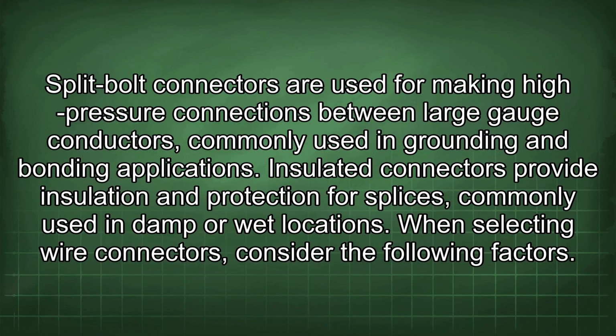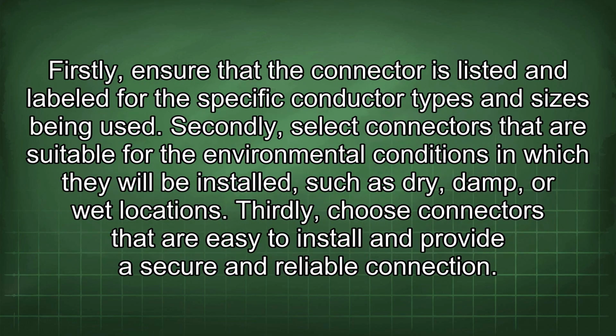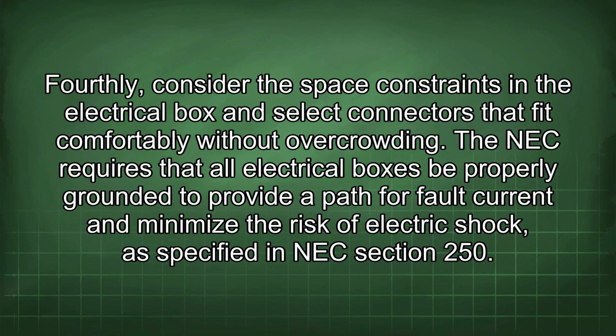When selecting wire connectors, consider the following factors. Firstly, ensure that the connector is listed and labeled for the specific conductor types and sizes being used. Secondly, select connectors that are suitable for the environmental conditions in which they will be installed, such as dry, damp, or wet locations. Thirdly, choose connectors that are easy to install and provide a secure and reliable connection. Fourthly, consider the space constraints in the electrical box and select connectors that fit comfortably without overcrowding.